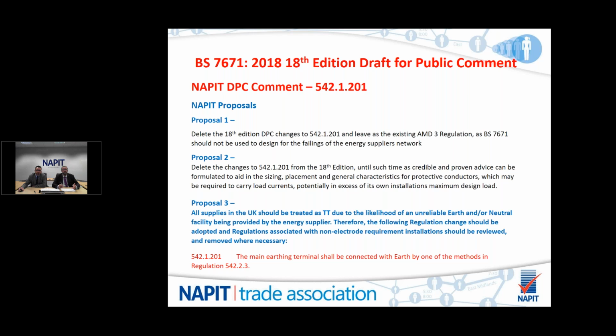Proposal 3. Just treat all supplies in the UK as TT. If there is a likelihood of an unreliable earth or neutral facility being provided by the energy supplier, which we feel is an unacceptable scenario, then just change the regulation to ensure that all installations are TT. And regulations associated with non-electrode requirement installations should be reviewed and removed where necessary. So we're recommending 542.1.201. Quite simply, the main earthing terminal shall be connected with earth by one of the methods of Regulation 542.2.3.